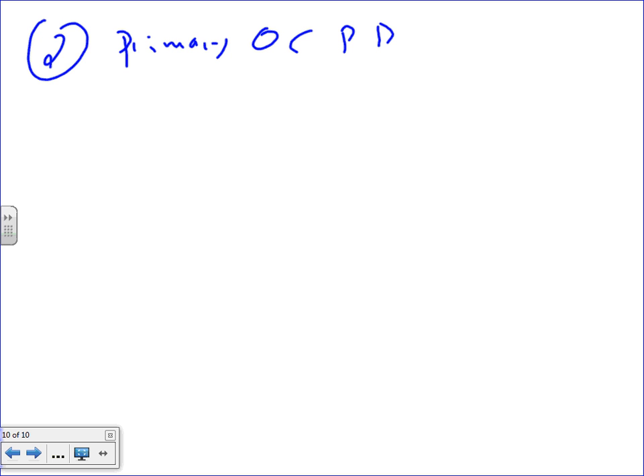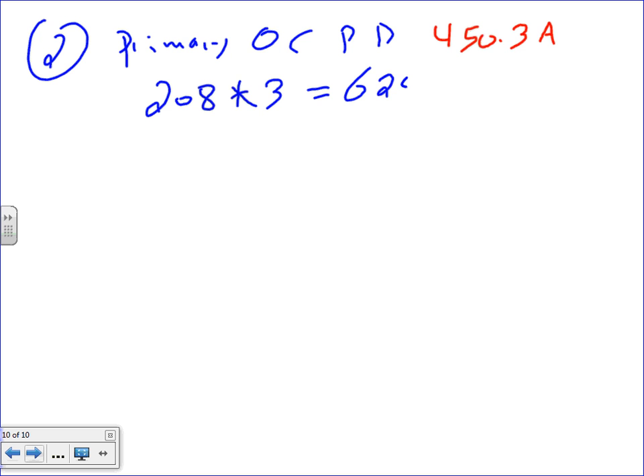The fuse, the full load current was 208, multiply this one by 3. Where did I get the 3? This is from Table 450.3(A). Why A? Because one of them is higher than 600 volts. If you do this, you're going to end up with 624 amps. You're going to take this one to 240.6, and you're going to end up with, beautiful.